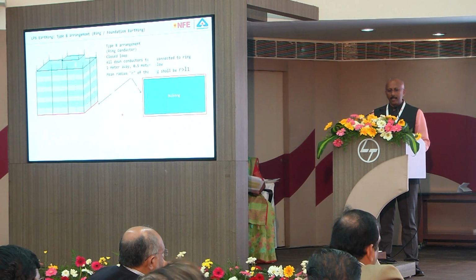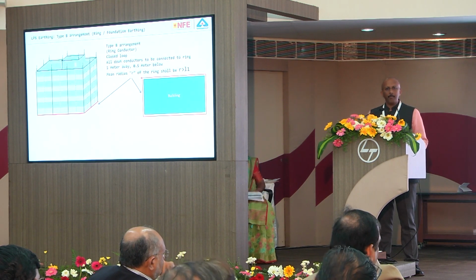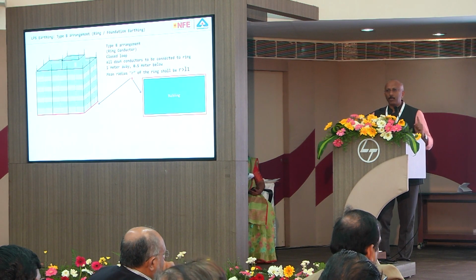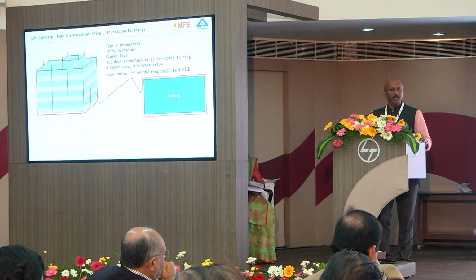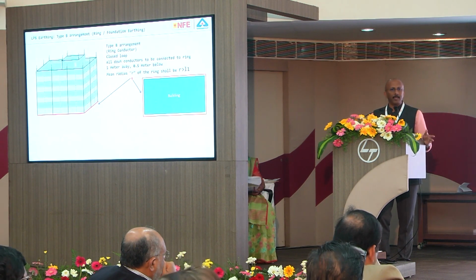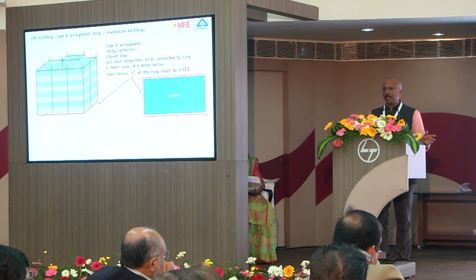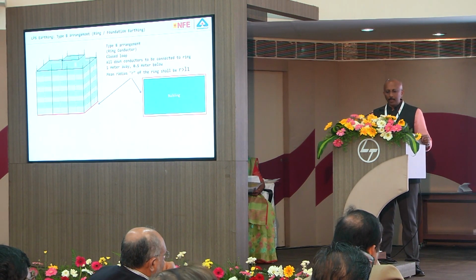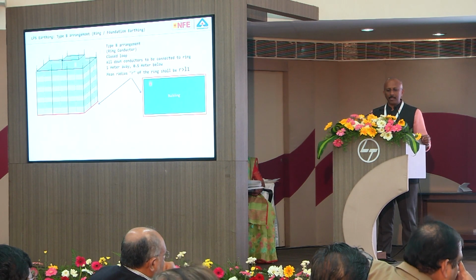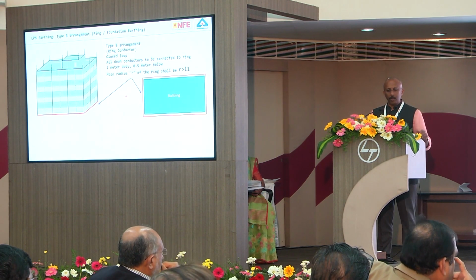Ring. The best way is to make a ring all around the building, which is called type B earthing. Ring earthing means a ring, please note, ring is closed. It is not open. If it is open, if you didn't connect it 100%, then you have to treat it as a type A earthing. You cannot treat it as a type B earthing. So now it has to be a closed loop. All down conductors shall be connected to this ring, and preferably this ring is 1 meter away from the building, 0.5 meter below the soil.